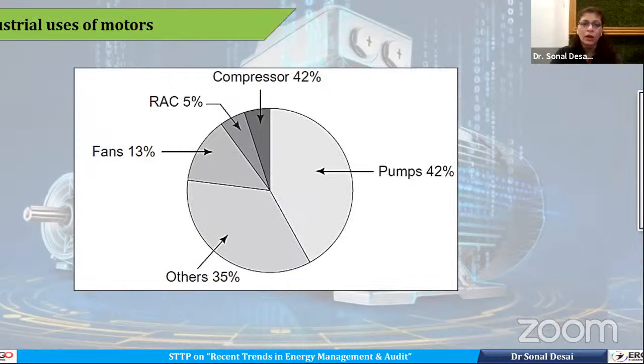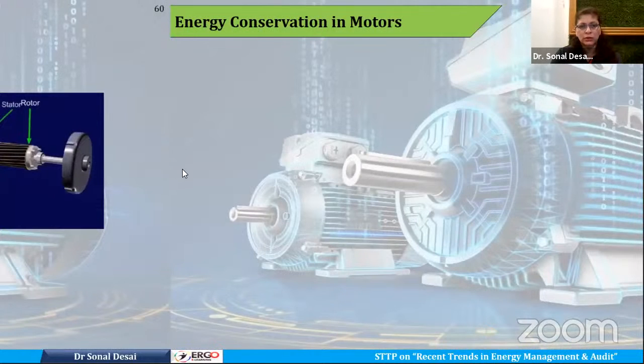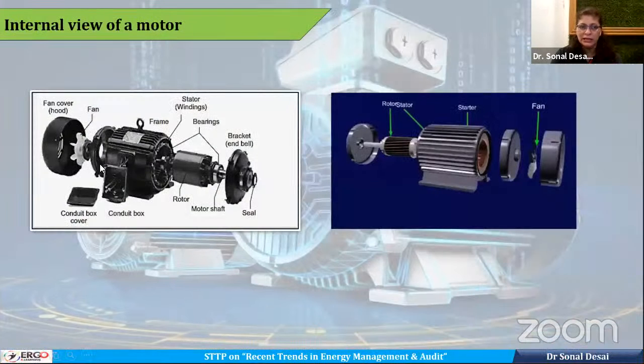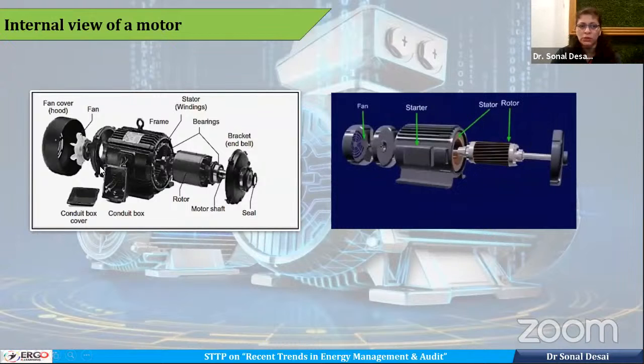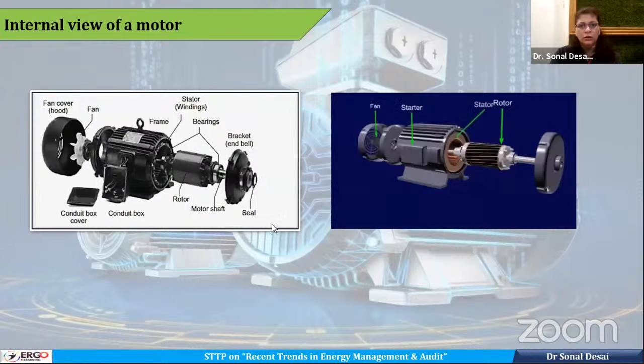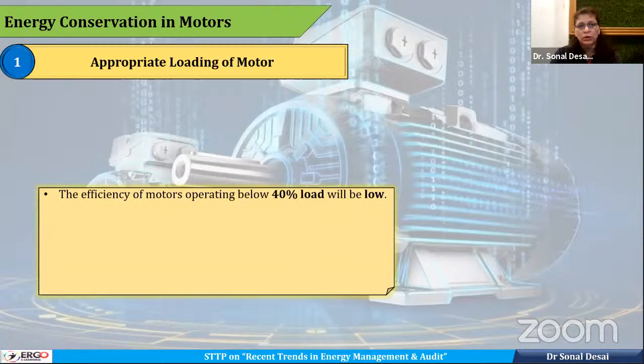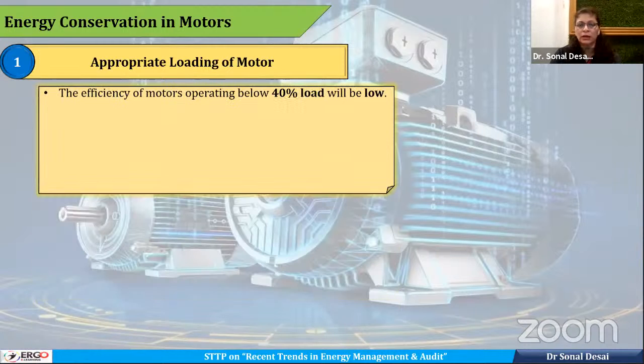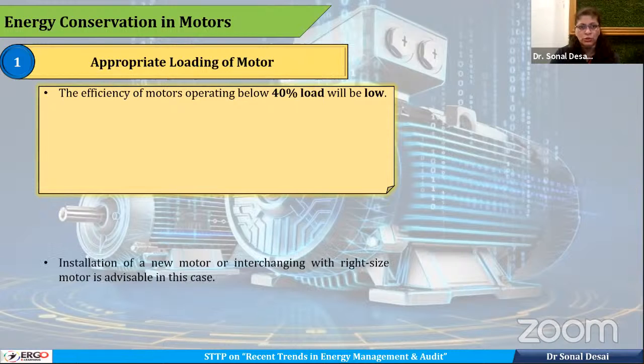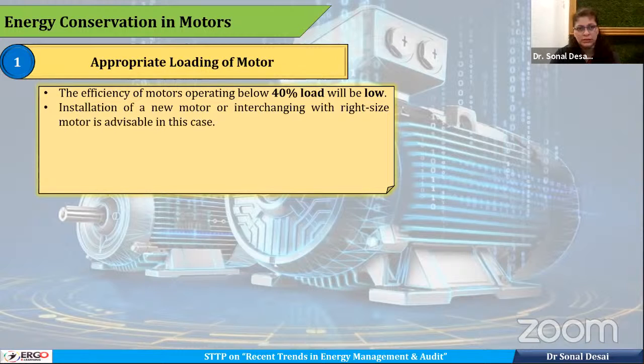If we talk about the internals of the motor, it is like this. Motor has internal components. There is a rotor, stator, bearings on the end, a fan for keeping it cool, insulation, and then some other accessories. What is important in motor is whether it is loaded at an appropriate rate or not. Whenever a motor operates below 40% load, its efficiency will be less. So it is a must that the motor should always be loaded at least at 40% load.